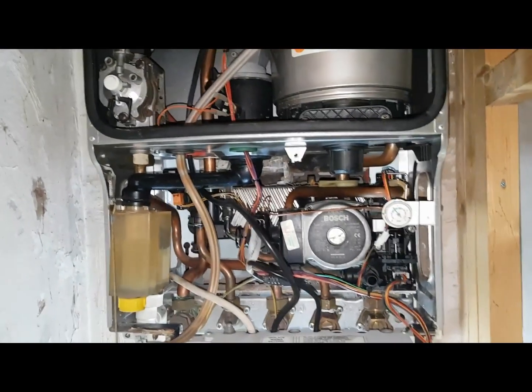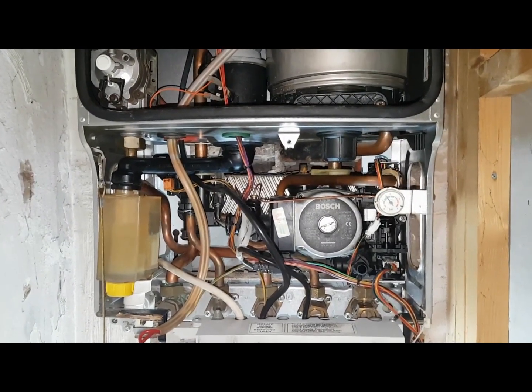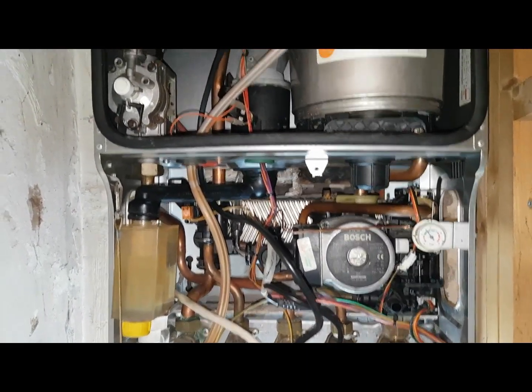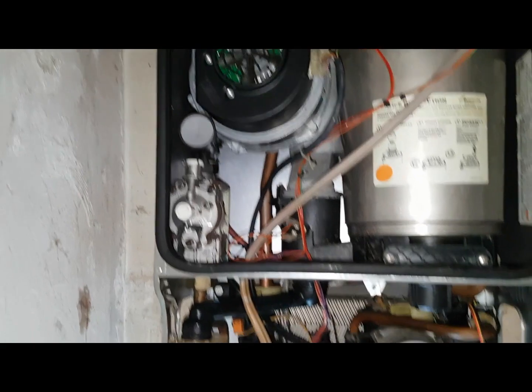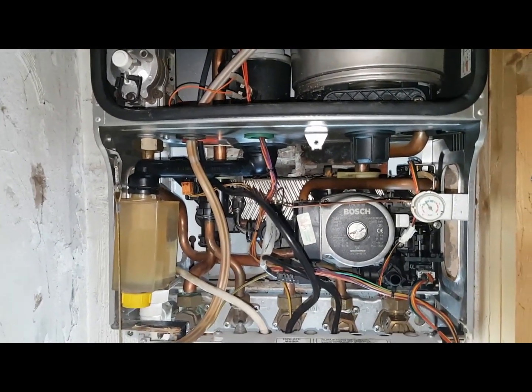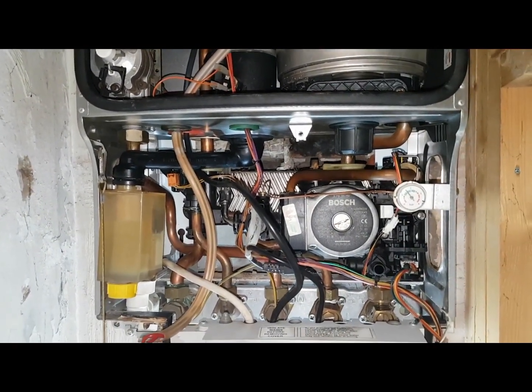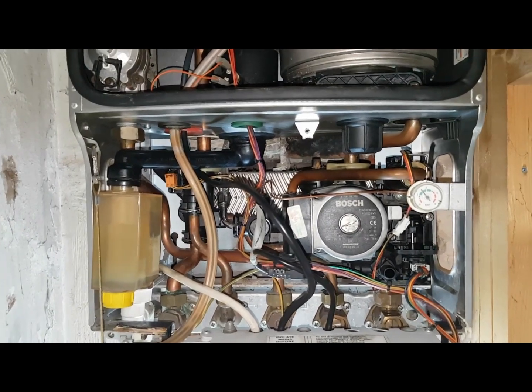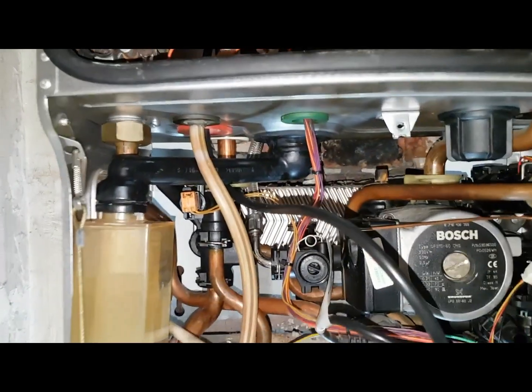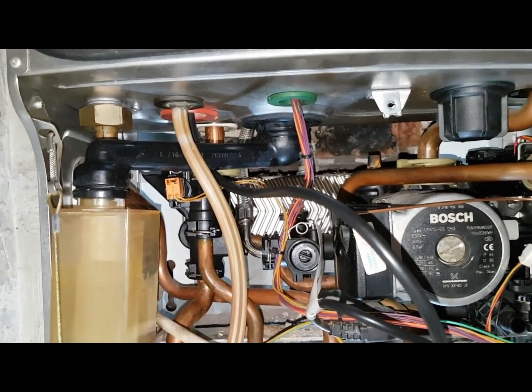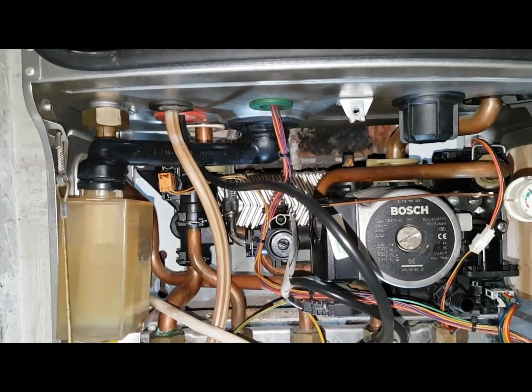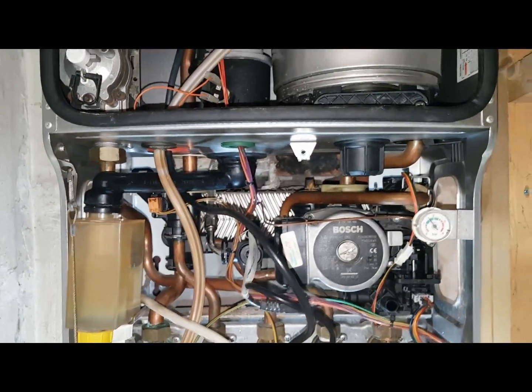If you run it in hot water mode and you notice the fan speed getting slow, but yet the taps are cold or lukewarm, that would suggest there's a blockage in the plate heat exchanger here, because it's restricted, so it causes a back of heat.